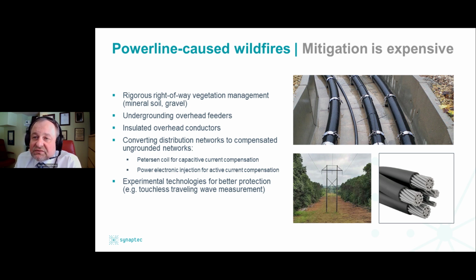There are some new technologies out there. One of them is to use ungrounded compensated networks, where you use the Petersen coil to squelch the capacitive fault current, and then add on top of it a power electronic based injection in order to counter the active component of the fault current. As a result, the idea is that you will reduce the fault current to below maybe 1 ampere primary, and that is claimed to be low enough to prevent ignition. That idea is out there, but it's very expensive. The numbers I heard are to the tune of $8 to $10 million per distribution substation.